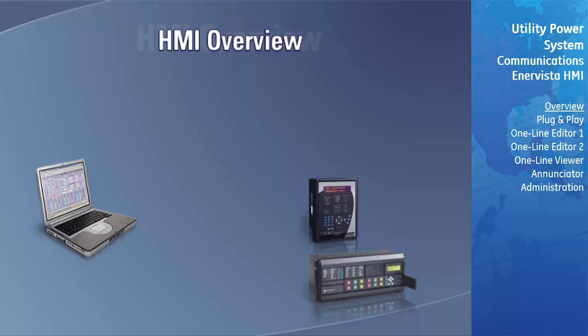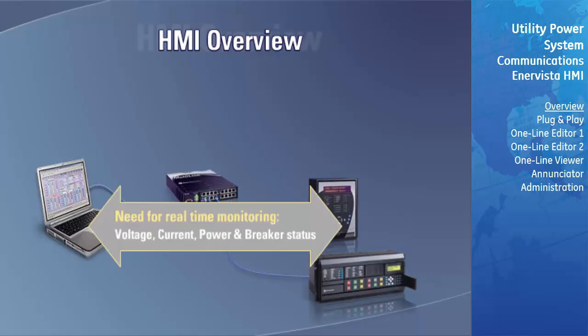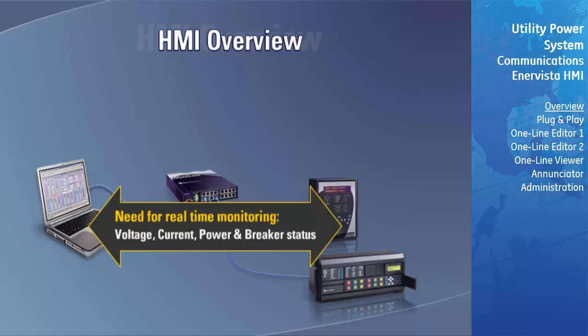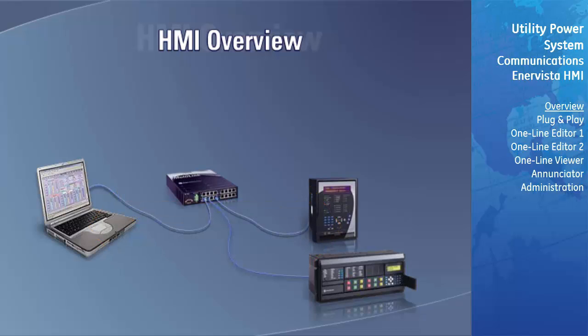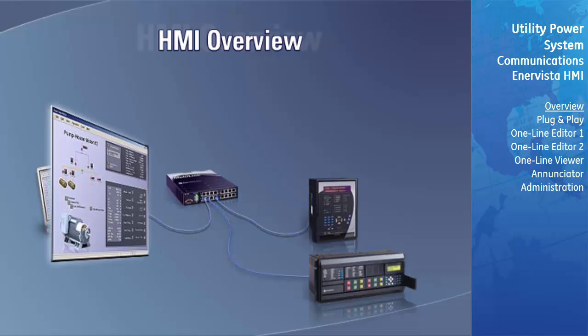Often, there is a need for real-time monitoring of protective relays and their power system quantities, such as voltage, current, power, and breaker status. There is also frequently a need to perform control functions, such as manually opening and closing a breaker. The system that performs such functions usually takes the form of a single or multiple computers running a special software package. The resulting system is referred to as a human-machine interface, or HMI.